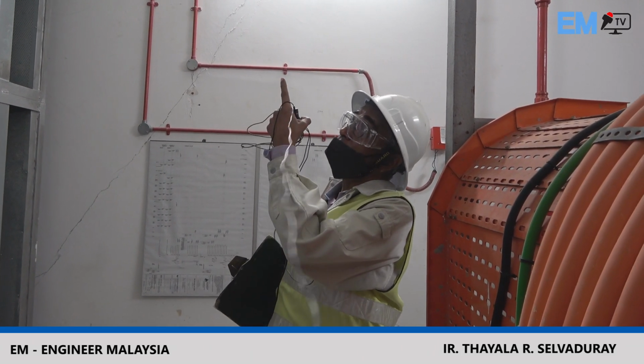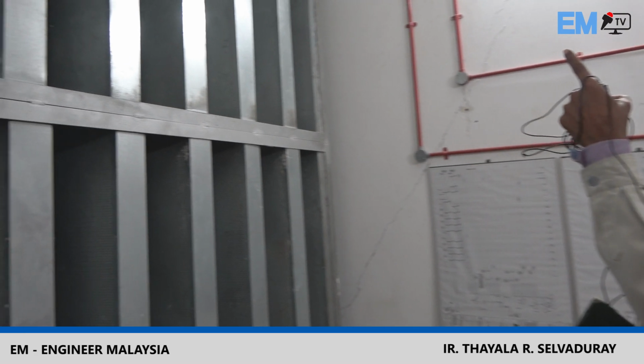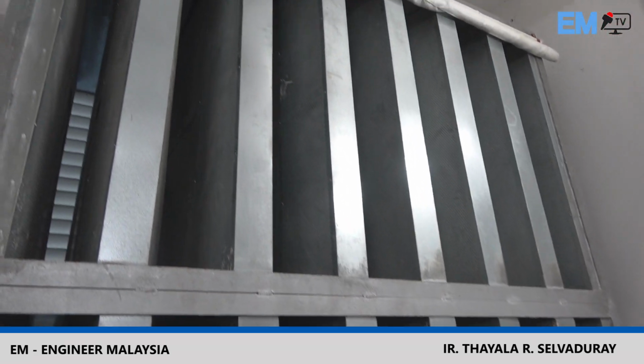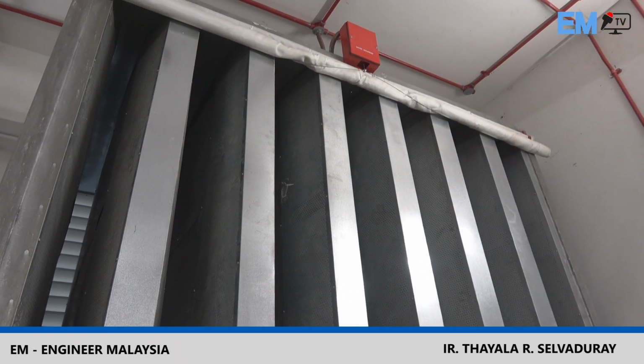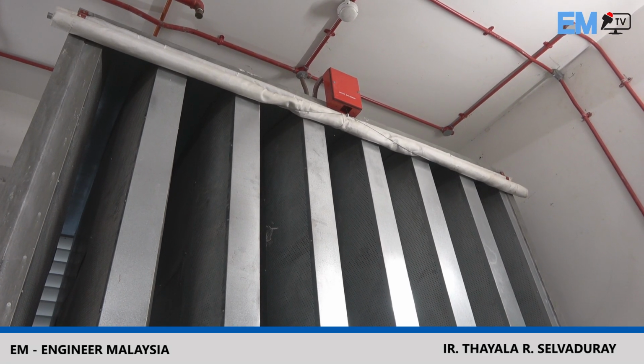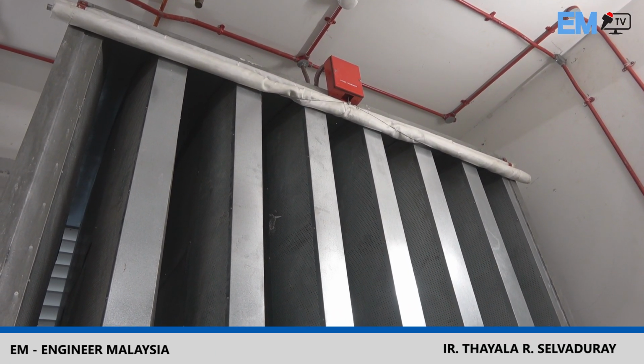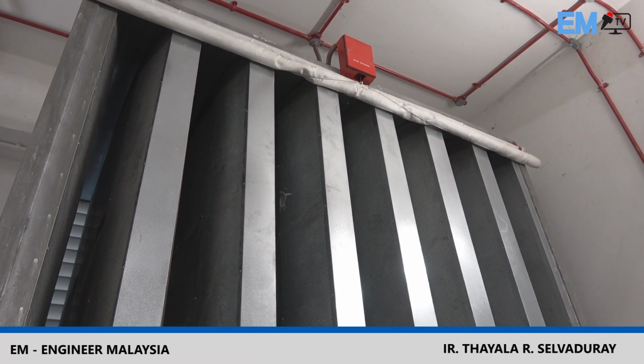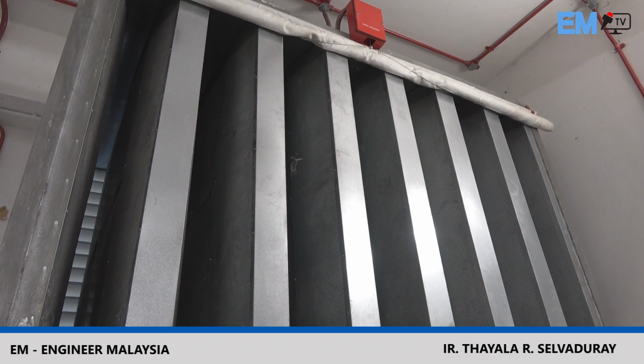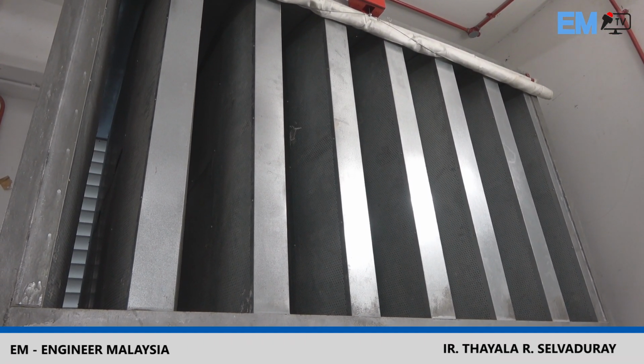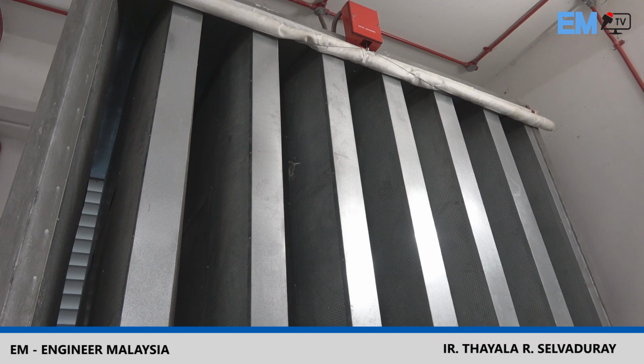Now when that happens, you have to make sure all air ventilations are closed. When you see up here, the air ventilation, right? This is the air ventilation for the exhaust. This curtain here will immediately drop. In other words, it starves this room of oxygen. When the room is starved of oxygen, that means there's no way for the fire to survive. So the carbon dioxide will suffocate the fire. That's how it works.